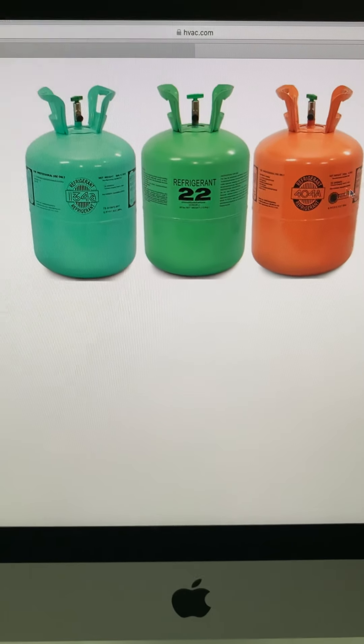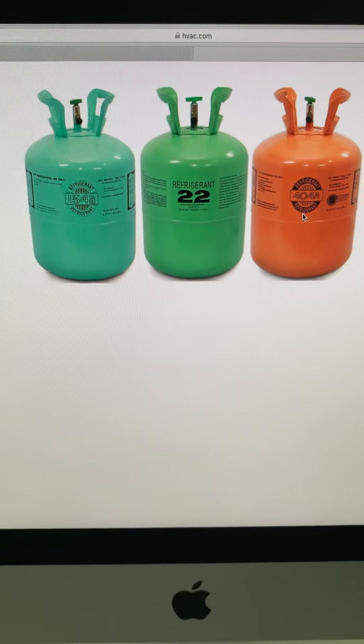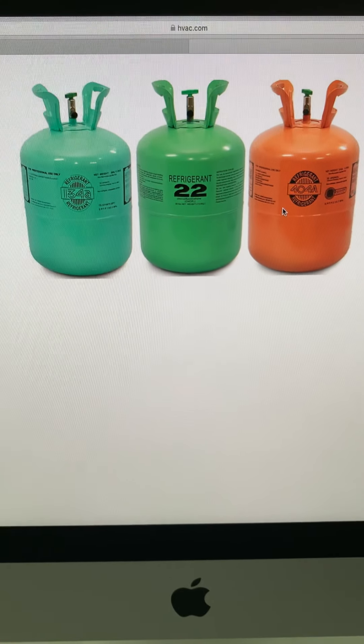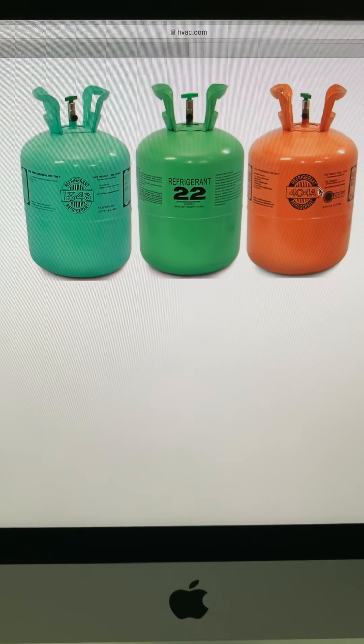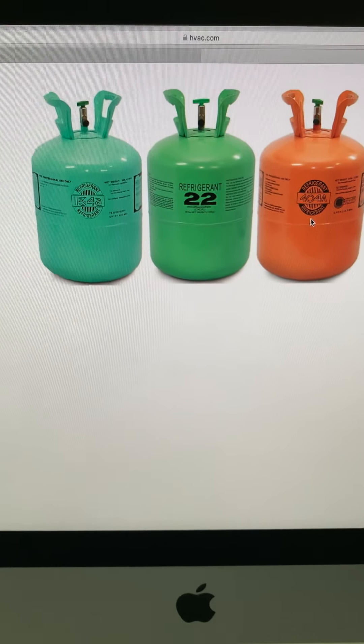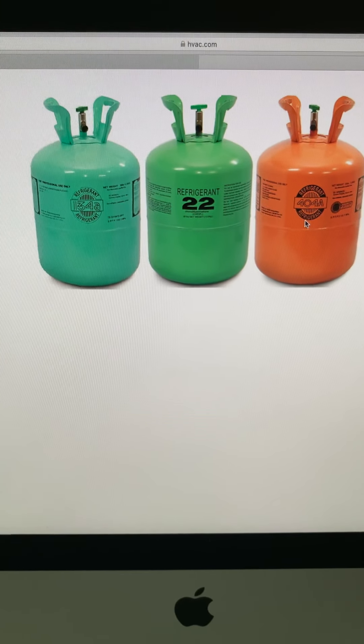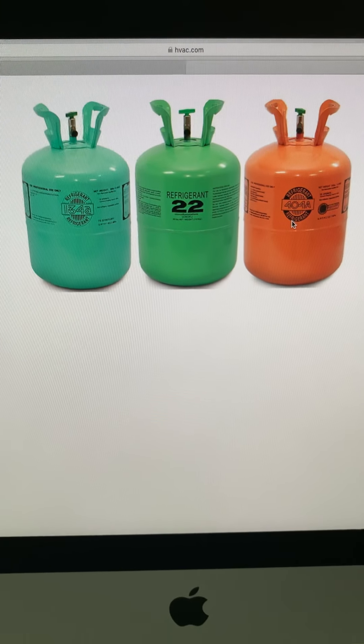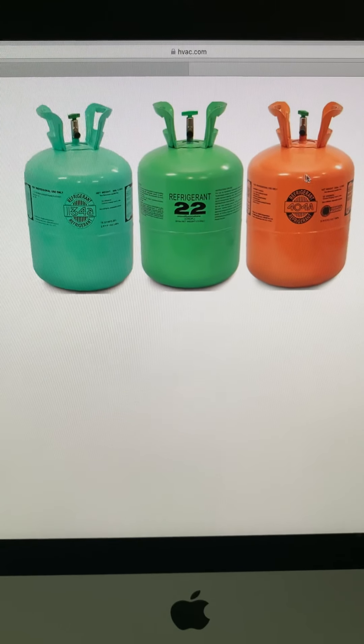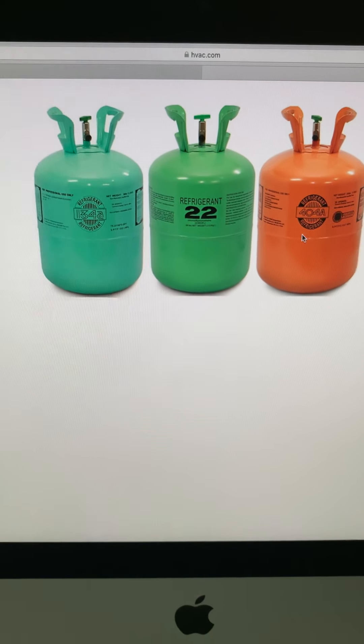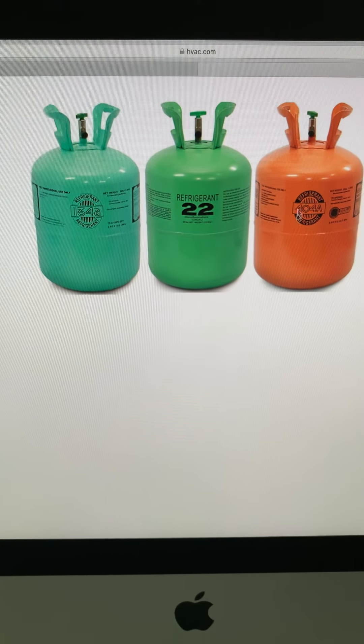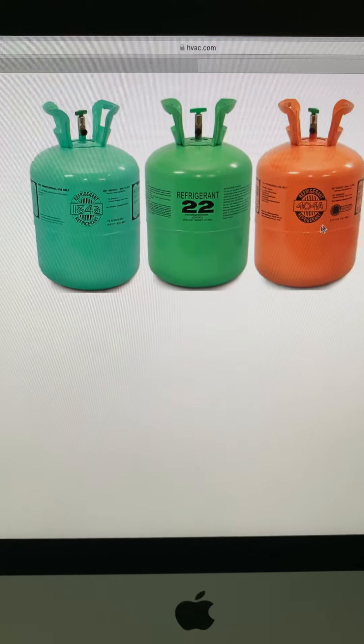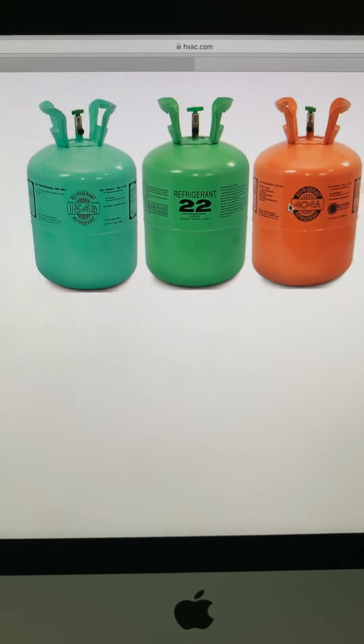you want to stay away from 404A. If you choose 404A, you're going to have to pre-cool that system early in the morning when it's cooler and keep that system running. That's what most ice cream guys do; they pre-cool their freezers.